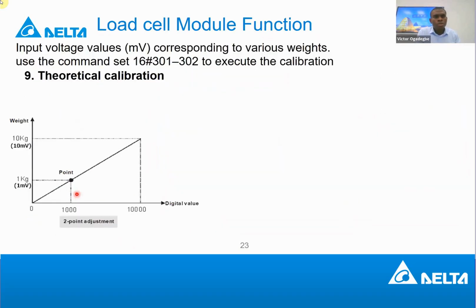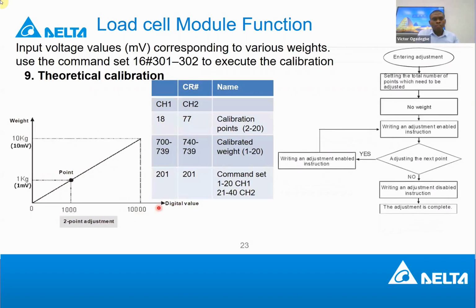And then number 9, the last function, is theoretical calibration. Instead of putting a real weight on the sensor, you don't do that. You already know the specification of the sensor: 1 millivolt, for example, is equivalent to 1000 digital value. If the sensor's internal circuitry outputs 10 millivolts, it means the weight applied on it is 10 kg. You can reconcile that. So if I measure that, I need a digital value of 10,000. So this is the flow.